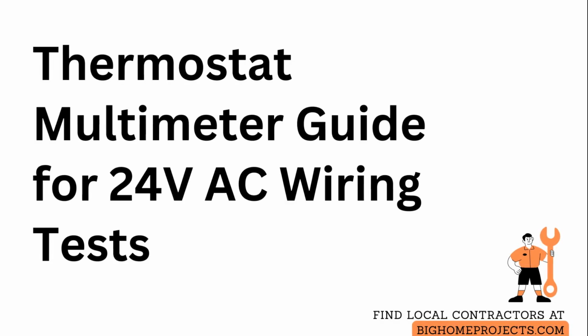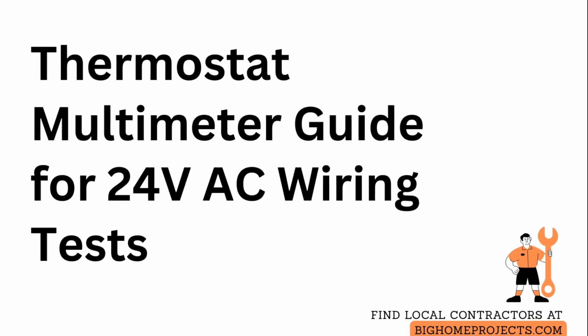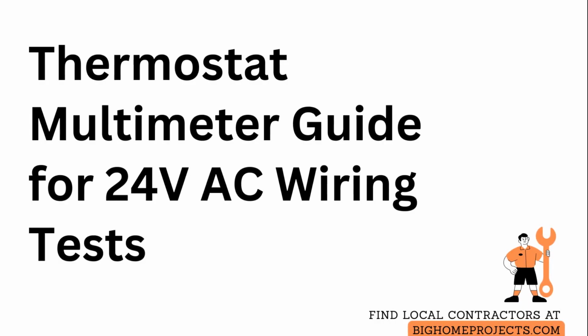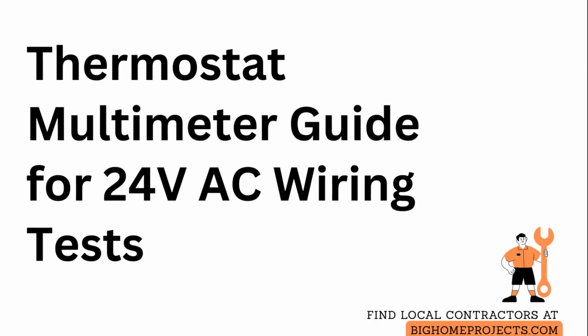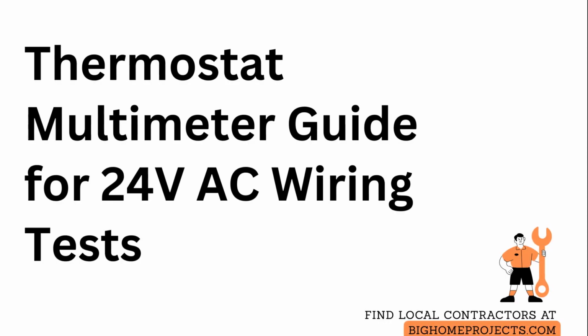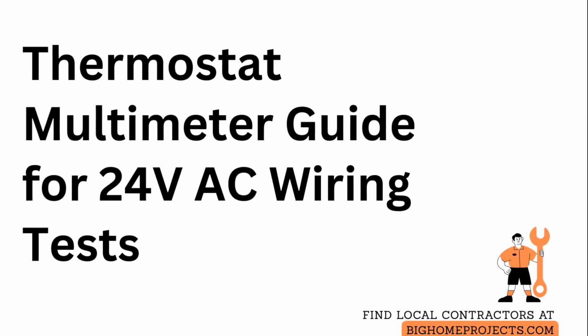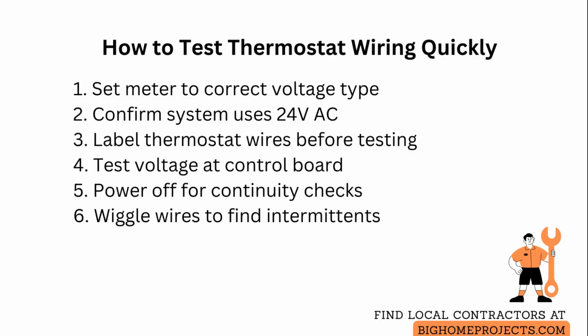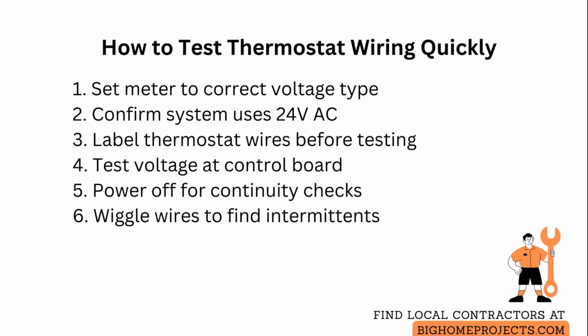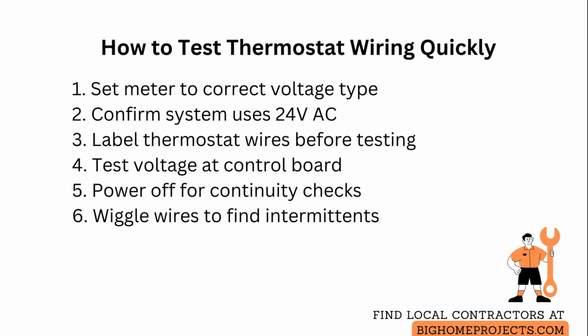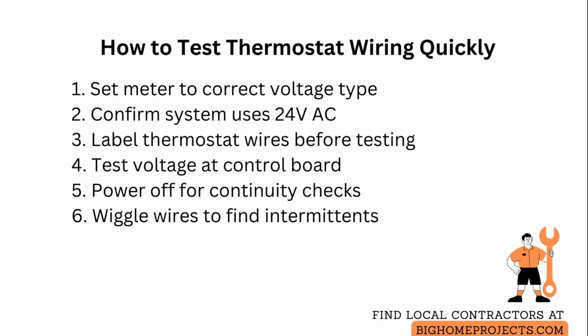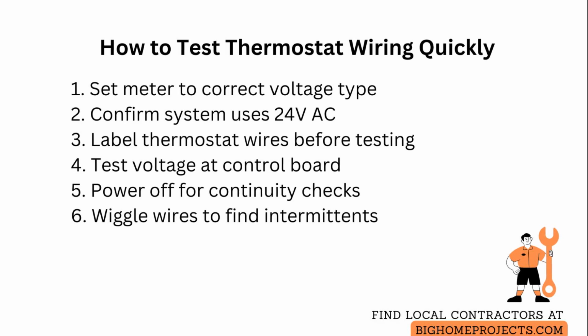Using a multimeter to test thermostat wiring provides definitive voltage and continuity readings that quickly isolate wiring faults and confirm whether the thermostat, transformer, or control board is at fault. Start by setting the multimeter to measure volts alternating current for typical heating, ventilation, and air conditioning transformer outputs, and use volts direct current when checking low voltage direct current systems. Many household thermostats use 24 volts alternating current, so confirm system type in the equipment manual before testing.